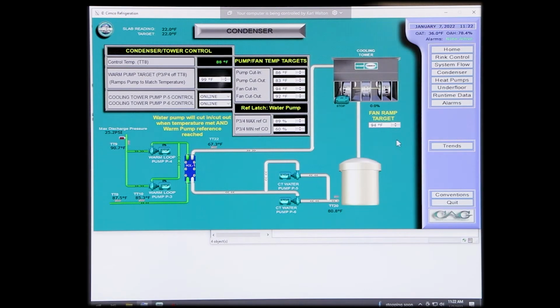In condenser screen, we have all of the commissioned temperature settings here: pump cut-ins, pump cut-outs, fan cut-in, fan cut-out, reference latch for the water pump, P3 or 4 max reference of cut-in, and P3, P4 max reference of cut-out. And these are percentages on the VFD, just how we control the discharge of the system. And you'll see as you watch the system run, you'll see how those come into play, maintaining the pressures and temperatures right where we need them.